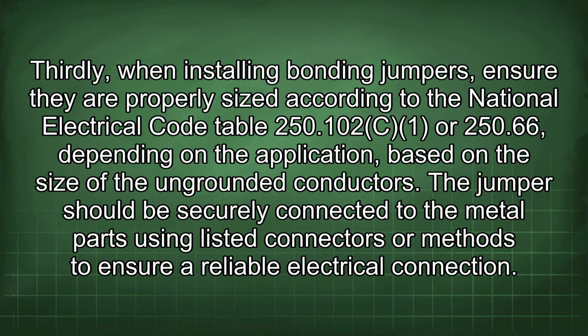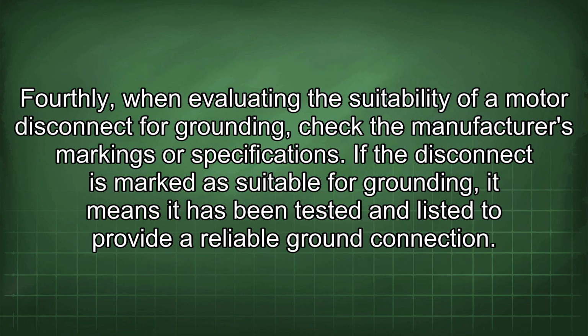Thirdly, when installing bonding jumpers, ensure they are properly sized according to the National Electrical Code Table 250.102(C) or 250.66, depending on the application, based on the size of the ungrounded conductors. The jumper should be securely connected to the metal parts using listed connectors or methods to ensure a reliable electrical connection. Fourthly, when evaluating the suitability of a motor disconnect for grounding, check the manufacturer's markings or specifications.